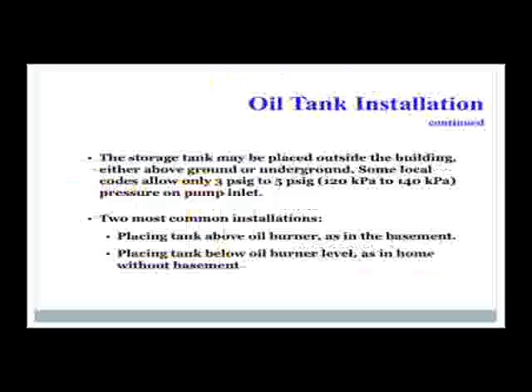The storage tank may be placed outside the building, either above ground or underground. Some local codes allow only 3 psi to 5 psi pressure at the pump inlet. The two most common installations of an oil tank are to place the oil tank above the oil burner, as in a basement, or to place the tank below the oil burner level, as in a home without a basement.